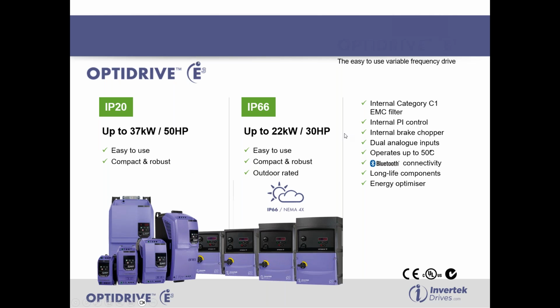In each of these products, we have an internal EMC filter, so that we don't have problems with electrical noise. We have an internal PI controller, so we can do pressure systems, temperature systems like that inside the drive rather than having to have an external controller. We also have an internal brake chopper, so if an application needs to stop quickly with high inertia, then we can do that also. We've got 2 analog inputs on these drives. We can operate up to 50 degrees C with the IP20 drive. So that means that the cabinets that we put the drives in require less cooling than they would if it was 40 degrees.